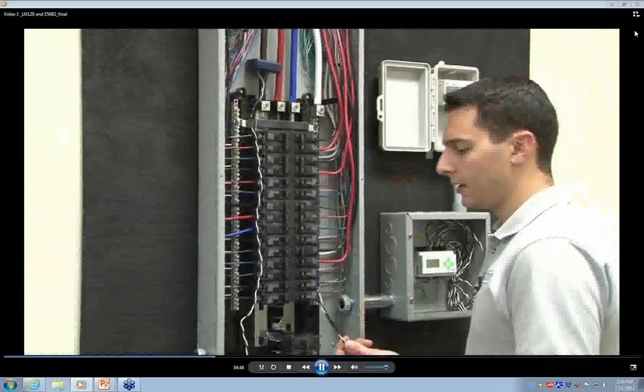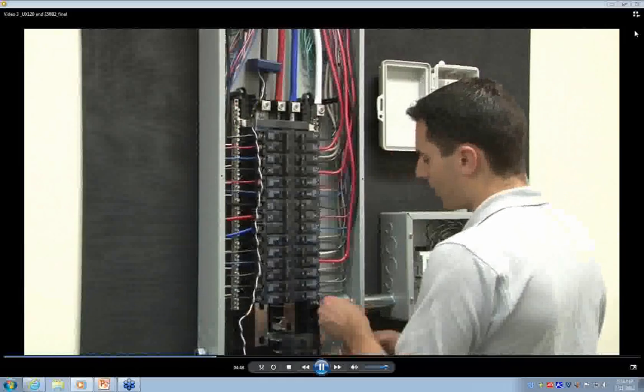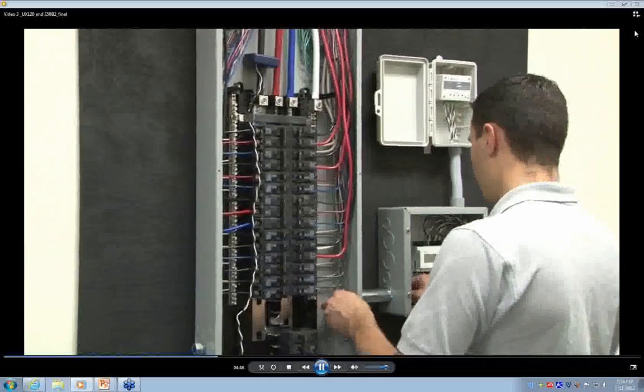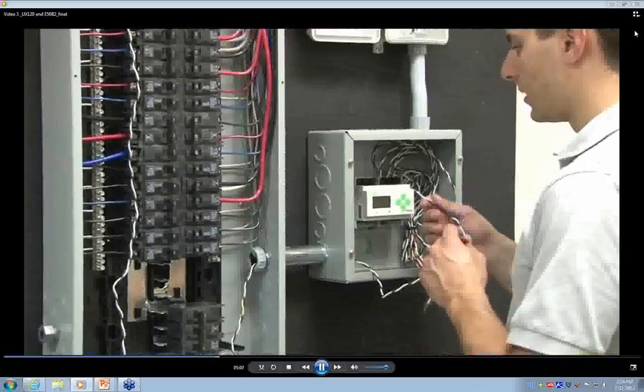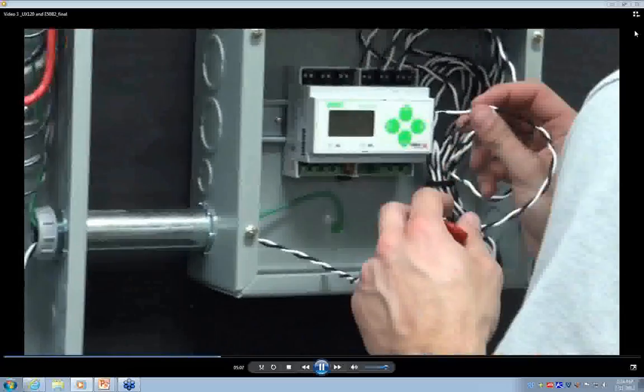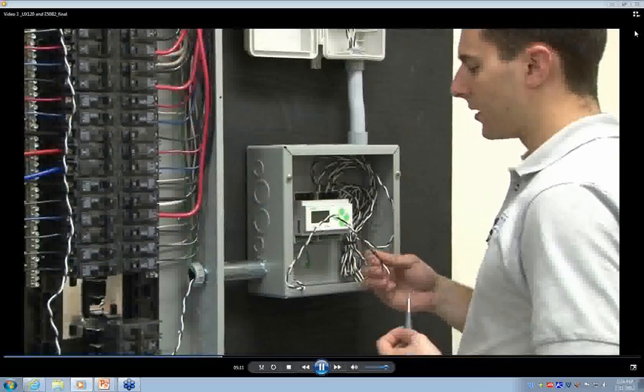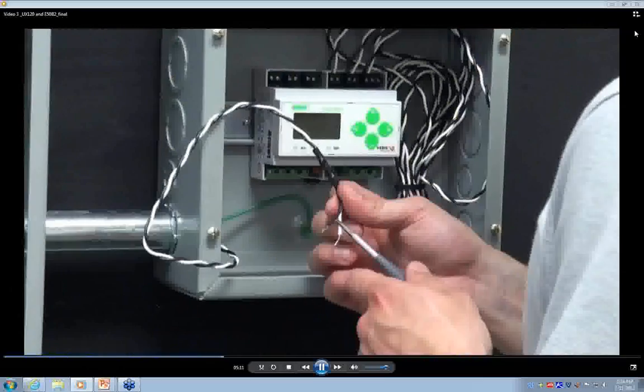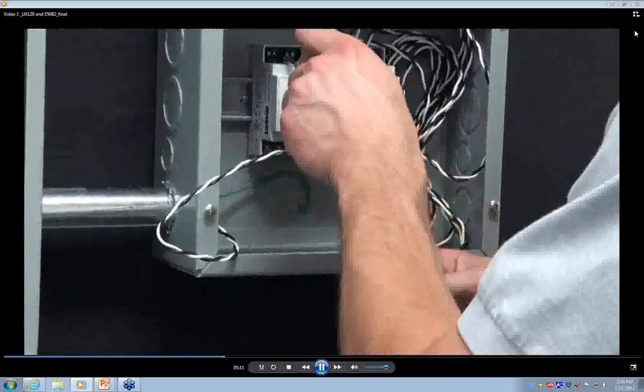And we run our CT conductor back through the 1-inch conduit to our E50B2 meter to the phase A CT terminal. Because these CTs are directional, it's important that the white conductor connects to the positive terminal and the black conductor connects to the negative terminal.